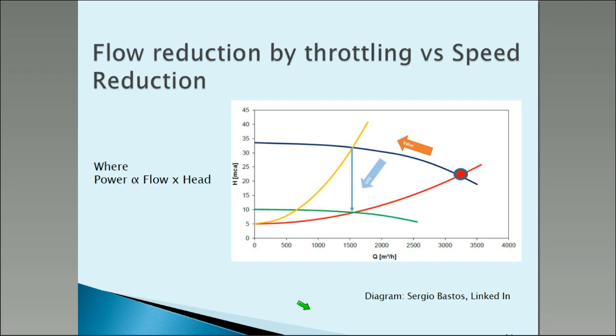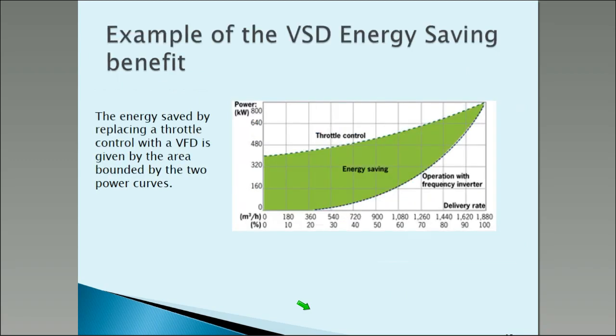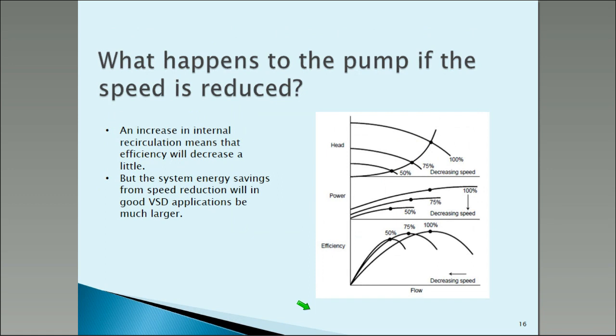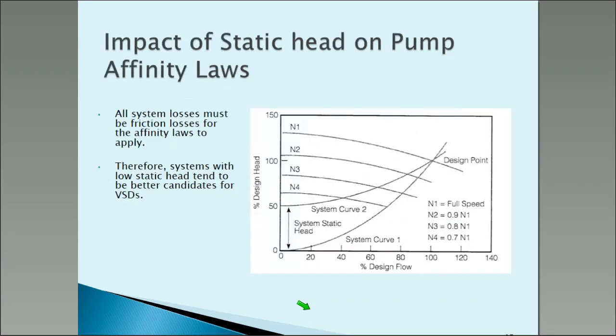That is why variable speed drives to reduce flow are really good. This curve emphasizes that — obviously, throttling will save some energy, but a variable speed drive or frequency inverter saves a lot more. The point is you don't have to reduce the flow by much to be in the big saving zone. Obviously the head will come down a lot, which is good. The efficiency of the pump will fall a little bit, but the loss of efficiency will be much less than what we're saving on the power. For most systems, you really don't have to worry about the actual pump performance itself.